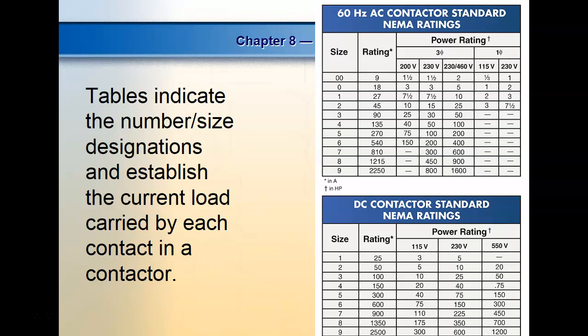Contacts are usually rated in current, guys. So this is going to be on the plate. They don't give you this information, and this would be a good chart. I don't know if ours has got that. Oh yeah, ours does. Did I pass ours around? No, our motor starter with the heaters on it. Where's it at? No, that's the manual.